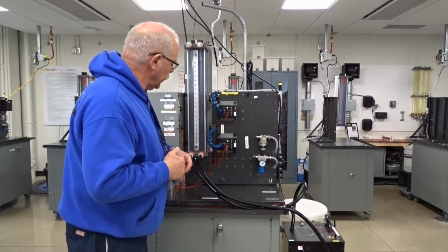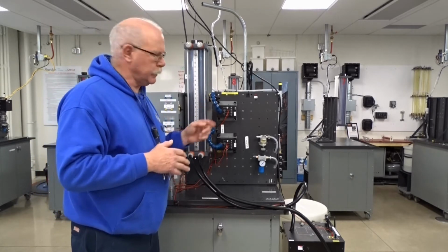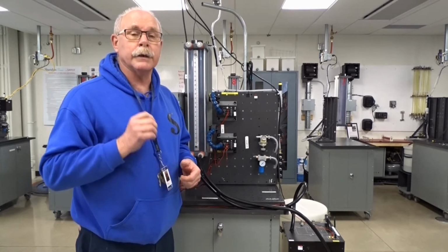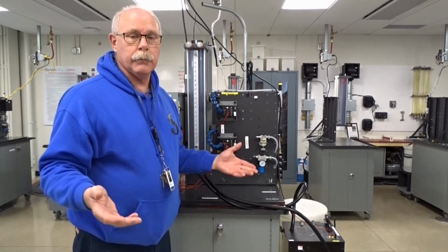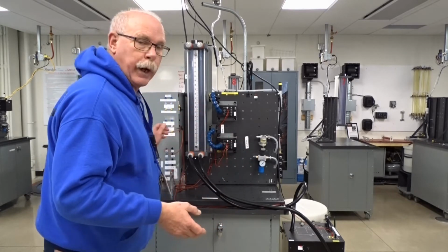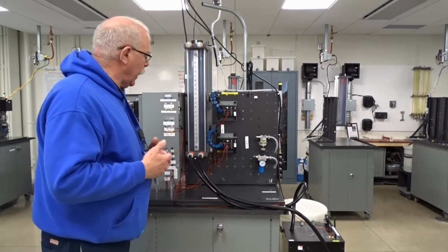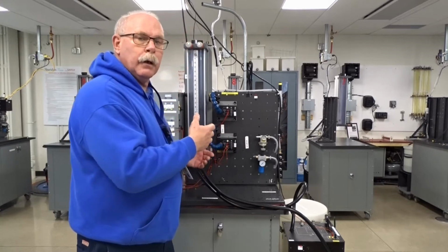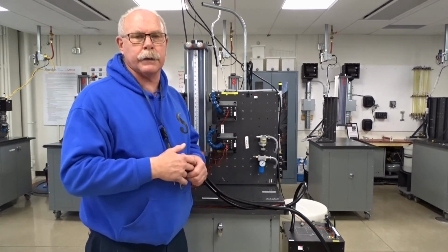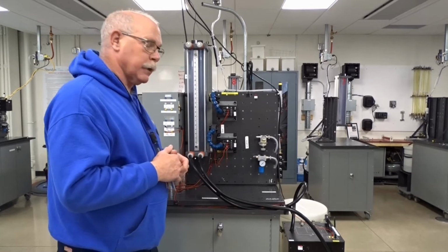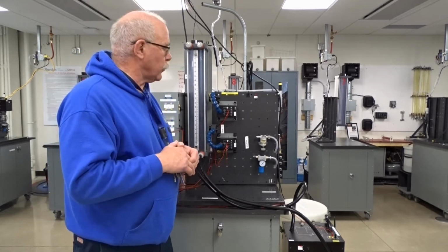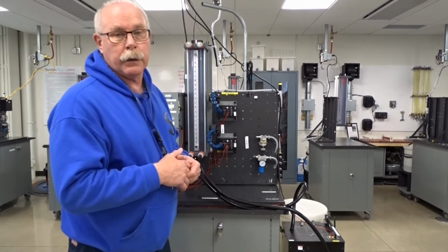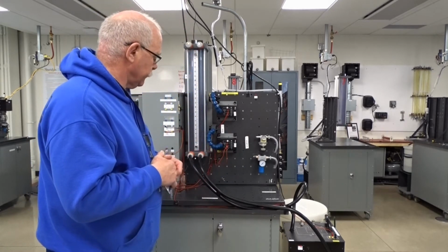What we actually have are 2 primary elements. They sense the condition of the process variable. There is no transmitter in this process. These feed directly into our control, and we don't use a signal from a transmitter. We do actually have a signal, and the signal is 0 for off and 24 volts for on. So we have a span of 24 volts and an offset of 0 in this case.